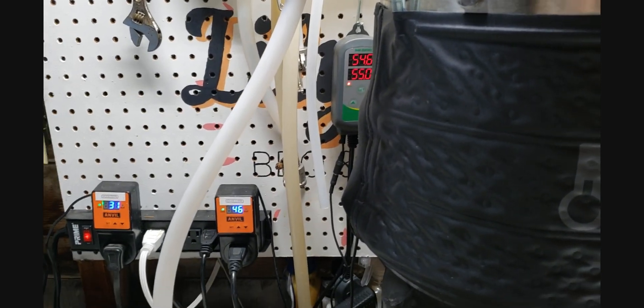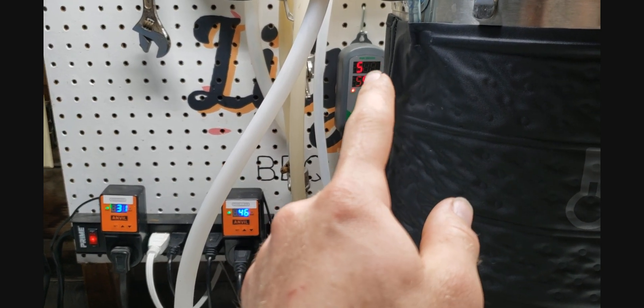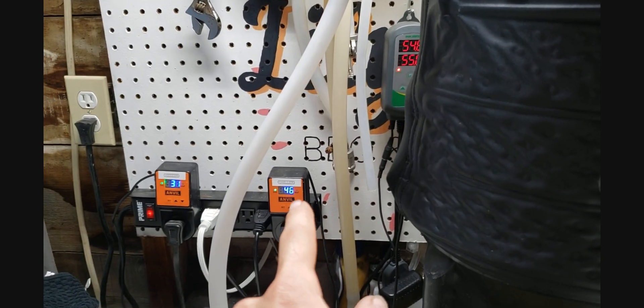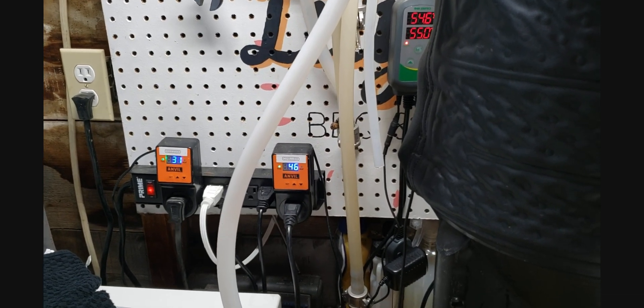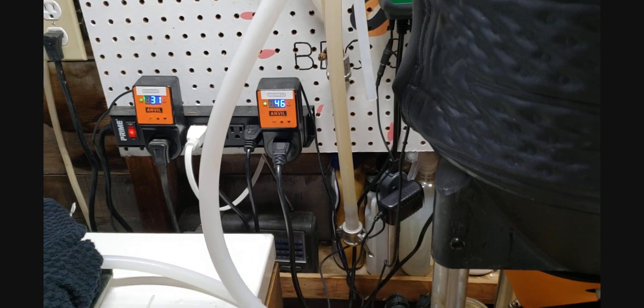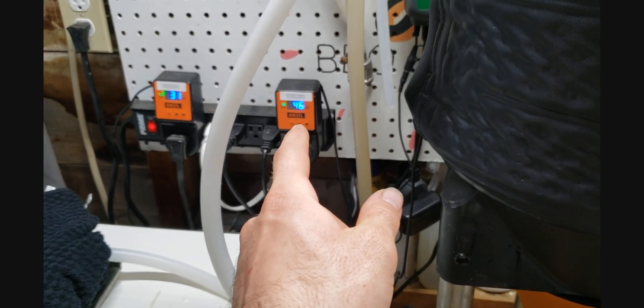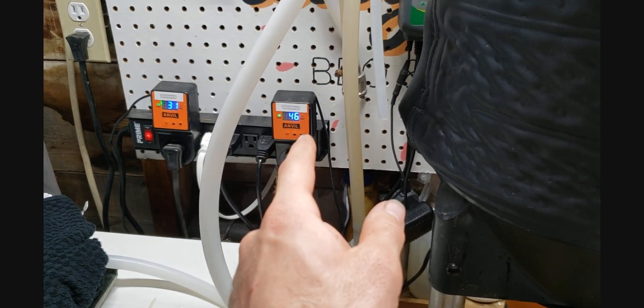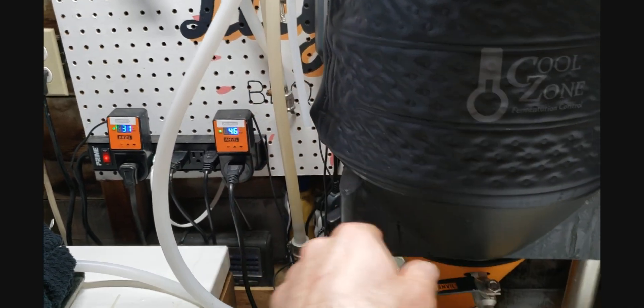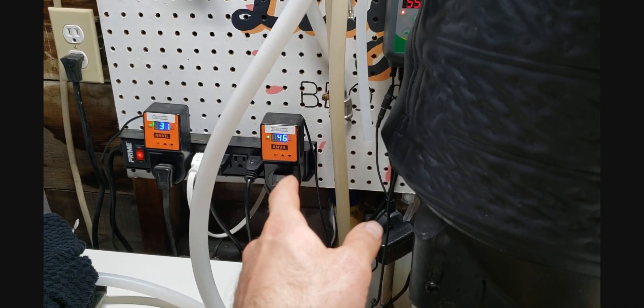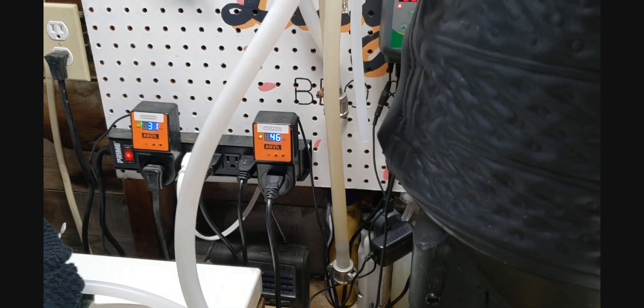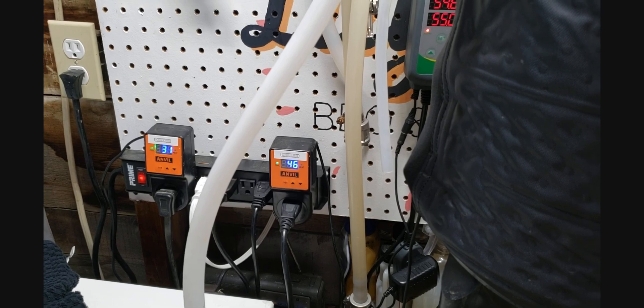So we want to watch for obviously this one to drop for sure, and we're hoping that our glycol gets a lot colder than 46. One thing that I'll typically do is wait for this to catch up. So we're at a big disadvantage right now because we're not running 16 degree glycol through the system. It's been running all day trying to keep up, and so we're running 46 degree glycol. So this will be interesting, but we're going to write all this down and start the test now.